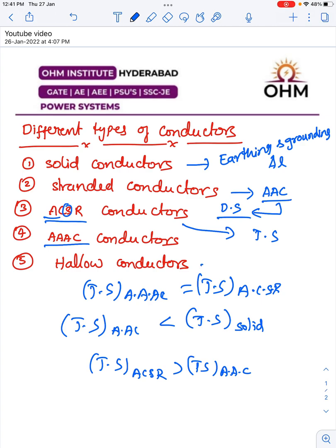Coming to hollow conductors — hollow conductors are preferred only for bus bars, nowhere else. Hollow conductors are also called tubular conductors. To summarize: solid conductors are not used in transmission and distribution, only for earthing and grounding. Stranded AAC conductors are used in the distribution system. ACSR conductors are used in the transmission system. Triple AC conductors are used for special applications — in the transmission system with lightweight towers, and in the distribution system for longer spans. Hollow conductors are used for bus bars.